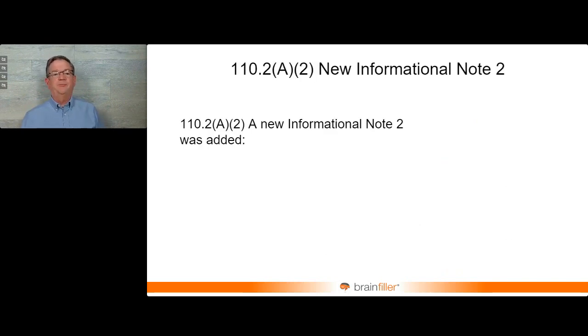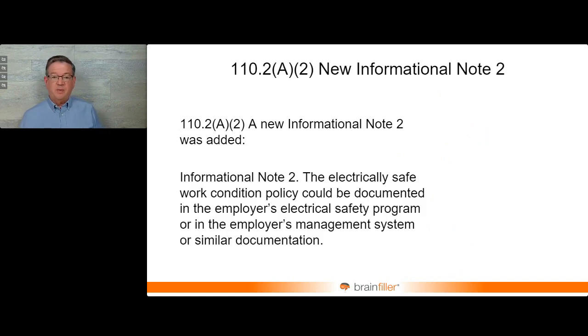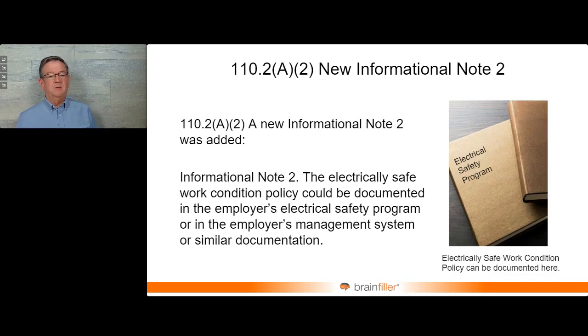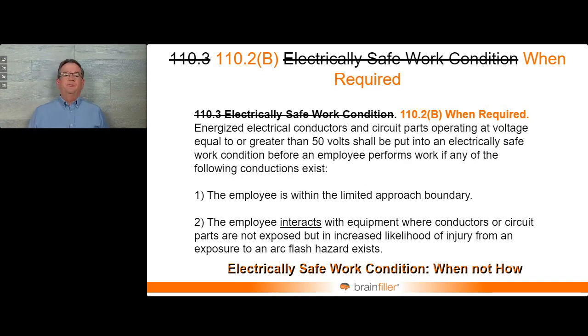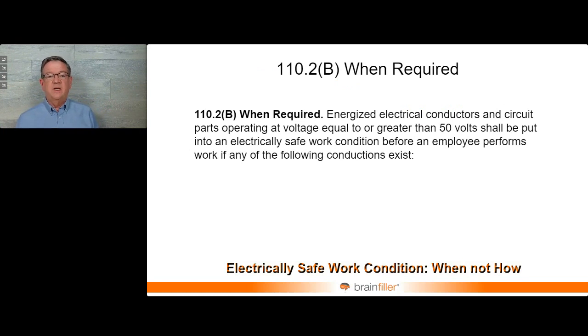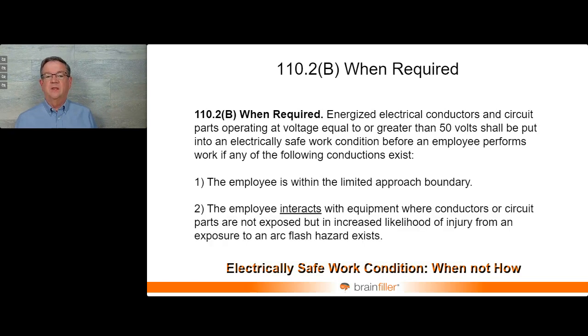An informational note was added that the electrically safe work condition policy could be part of an employer's management system, just ways to document it as an informational note. And then 110.2(B) hasn't changed a whole lot, but the titles, the numbers, things like that have changed. So what 110.2(B) actually says is energized conductors shall be put into an electrically safe work condition, 50 volts and greater, before anybody does any work, if they're within the limited approach boundary or they interact.